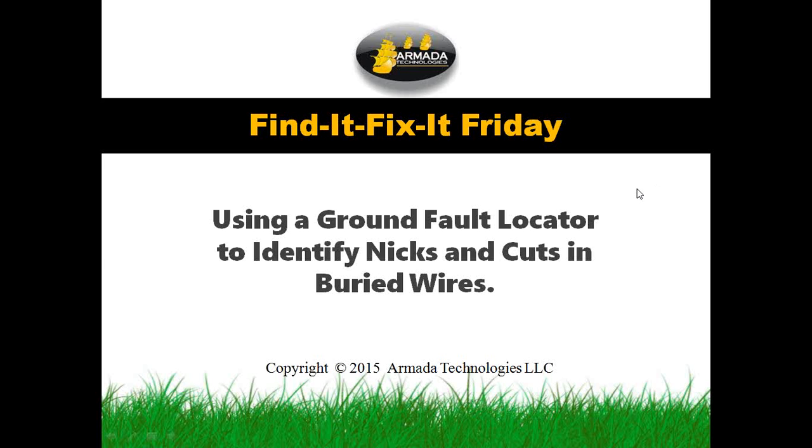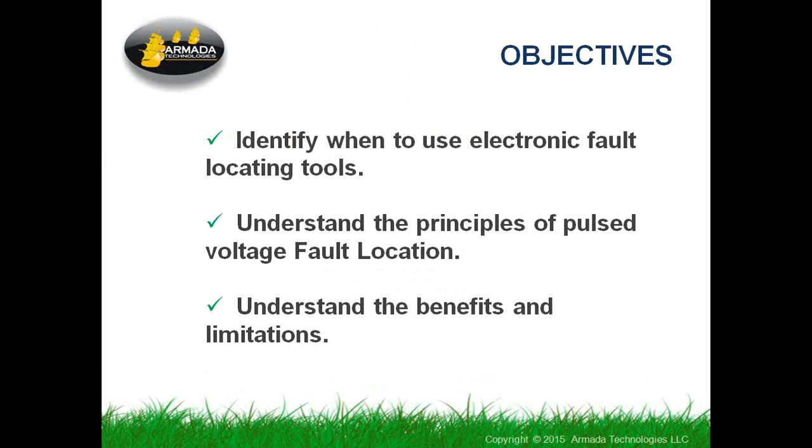So we're using a ground fault locator to identify nicks and cuts in a buried wire. Pretty important function. A lot of folks have not used this as much as they've used locators and other kinds of test equipment, but it is a very useful device in situations where you might be stuck. And by being stuck, I mean you can't see where the cut is, and you've obviously got cable damage.